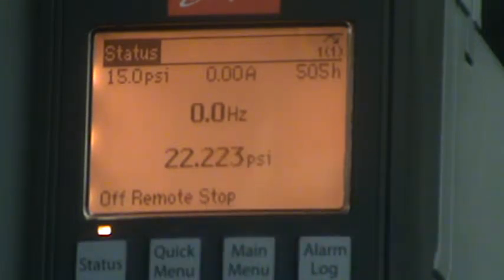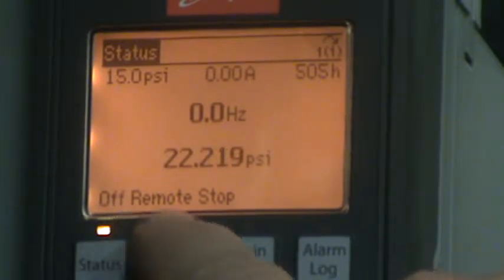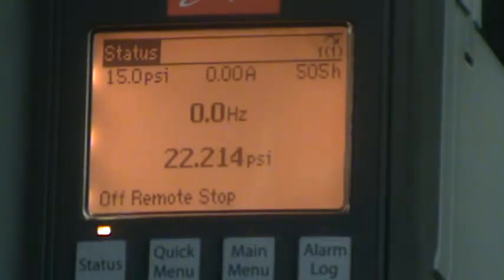The bottom lower level here is the actual PSI that is displayed out. Now right now you're seeing a display because your other pump is running. That number will change. If we set it at 15 PSI, you're never going to sit there dead on 100% 15 PSI, just stay there. There's always going to be some variation. And it's always going to be going back and forth, up and down. Down here at the bottom is off remote stop. It's stopped because we have it off. The other thing it can say is auto remote ramping, auto remote running.